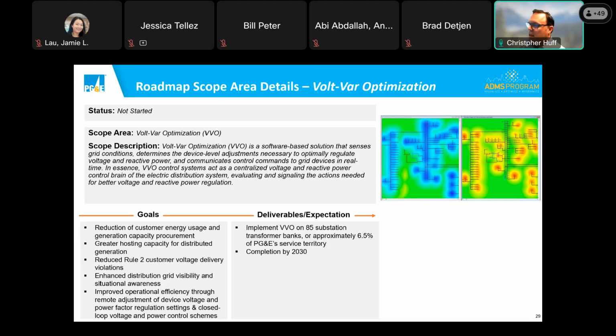These devices can essentially hunt, and it's difficult sometimes for them to coordinate under very specific scenarios, as well as they have impacts to neighboring feeders on the same bus. Volt-var optimization really centralizes that approach, bringing all this telemetry into a centralized location on that associated model, allowing the system to run various calculations and formulas and optimize the operation of these devices holistically as one, so that all parts of the system are accounted for when a solution is identified. This reduces customer energy usage, as well as the potential of Rule 2 violations, which are voltage violations for our customers, improving power quality and the operational efficiency of the devices by minimizing over-operation and undue wear and tear on the switching mechanisms.